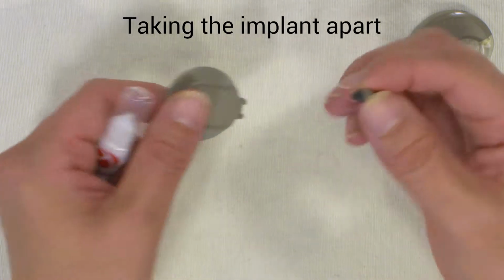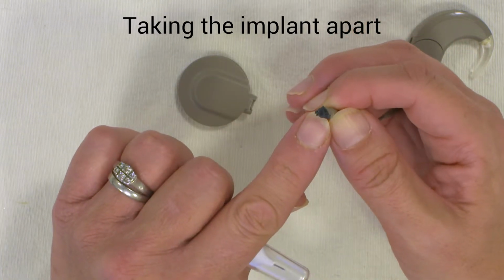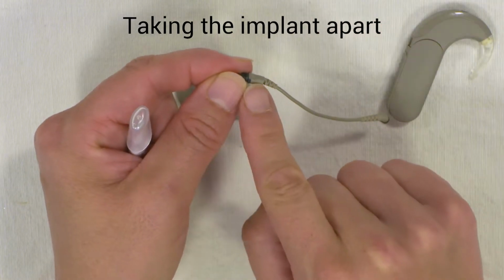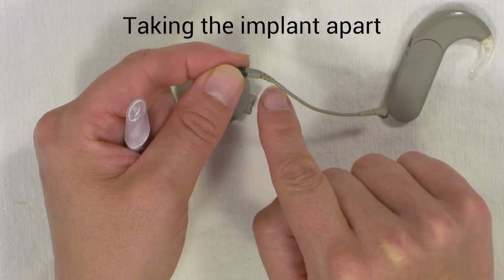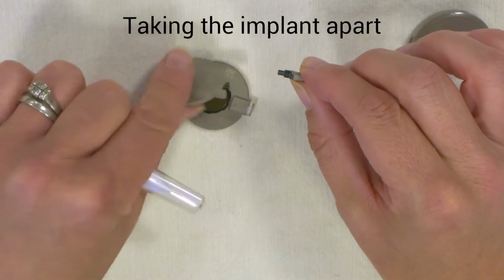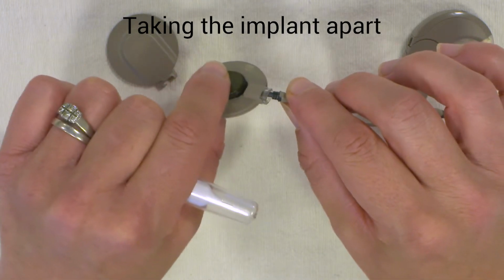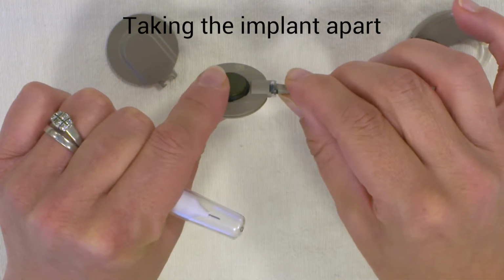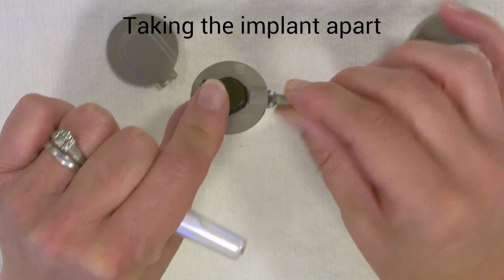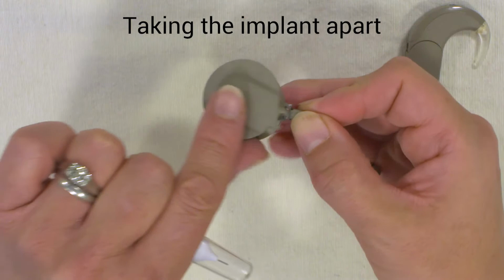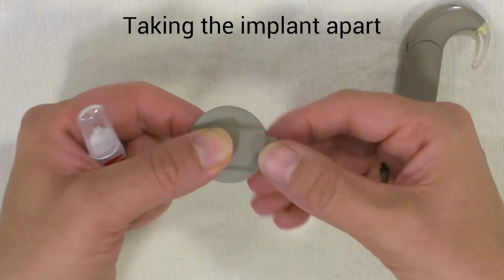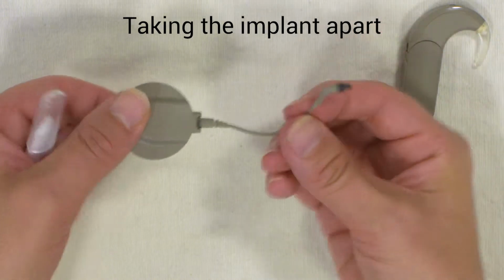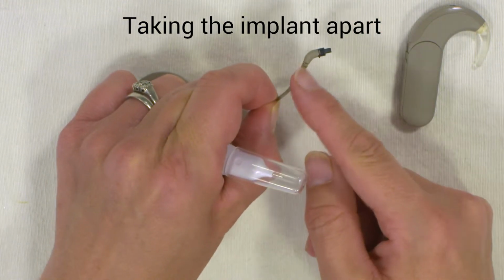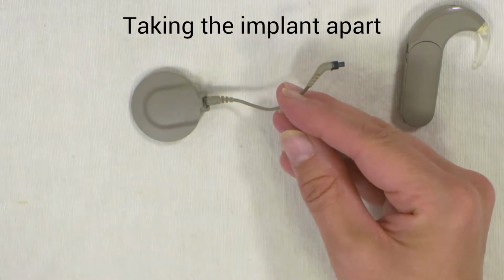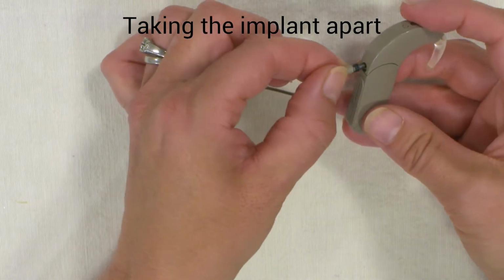To put it back in, you need to line up the coil lead at the right angle. So here you can see it slopes downwards. Take it like that, and slide it back in to the coil. You can then click the cover back on. The other end of the lead, again, make sure the lead is coming downwards, and you can slot that back in to the processor.